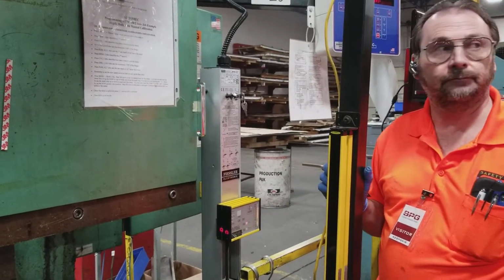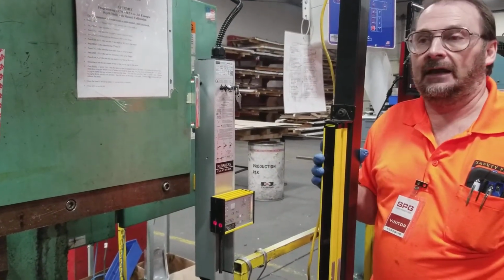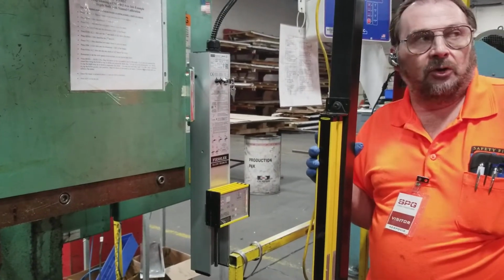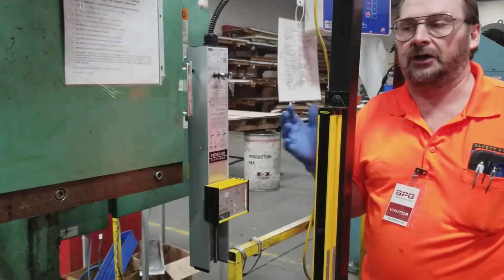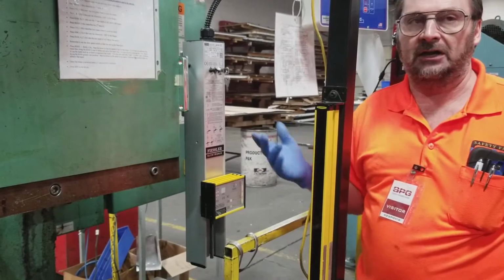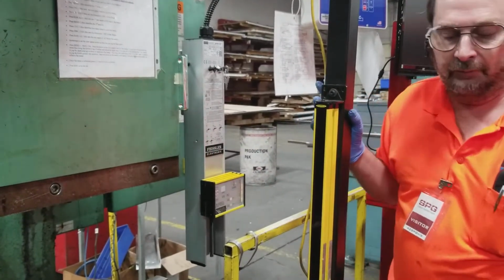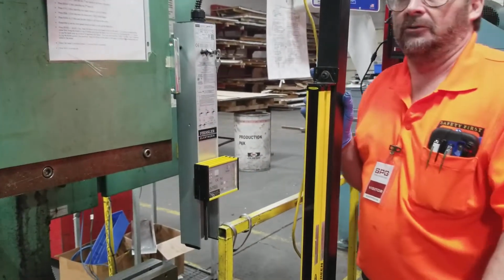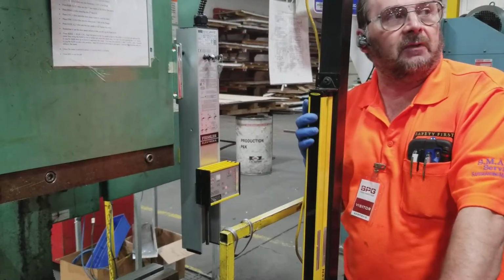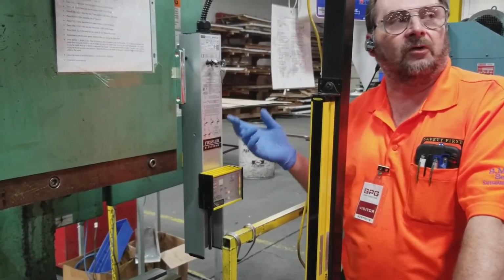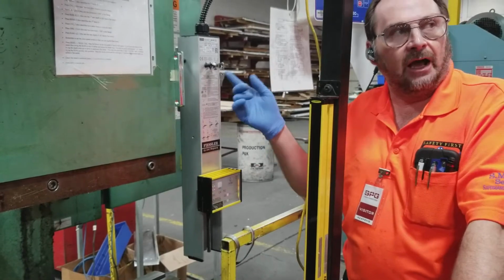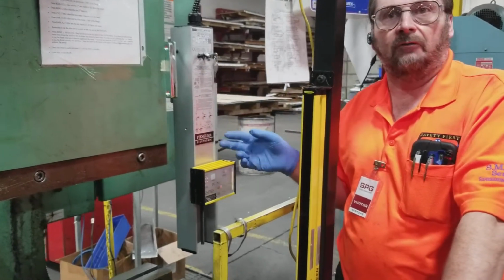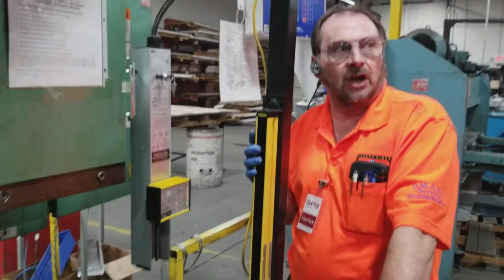Do you have to calibrate that every day? Any time that you change the upper tooling out. That's a good question. Anytime you change that upper tooling out, you need to calibrate. If you leave the machine longer than 30 minutes, we recommend you calibrate because you never know who's come over here showing a buddy how to run it up and down or whatever. So you may waste a lot of time if you don't.